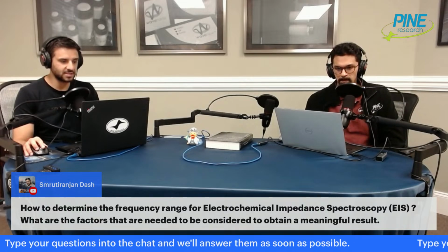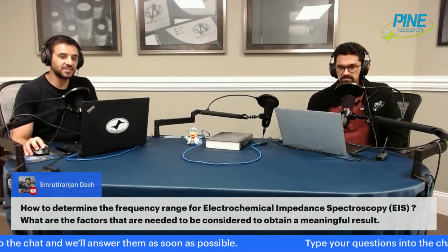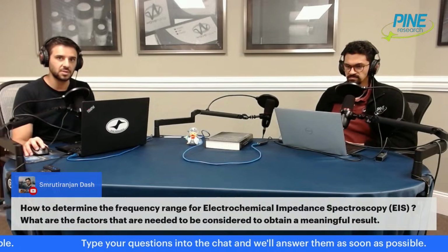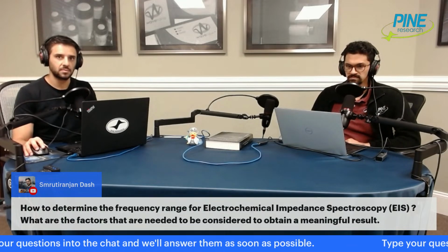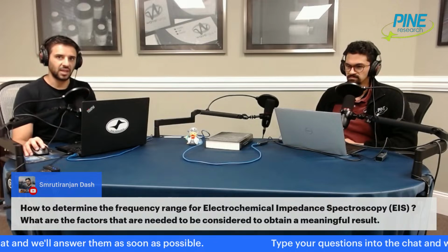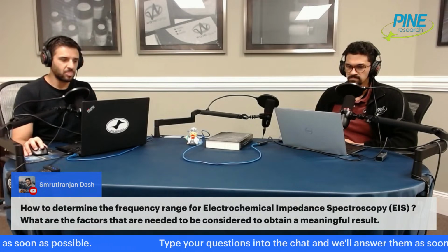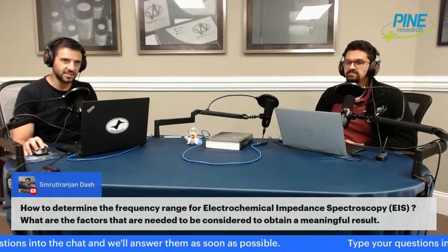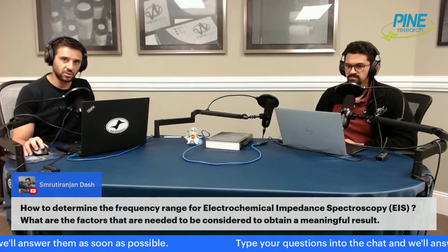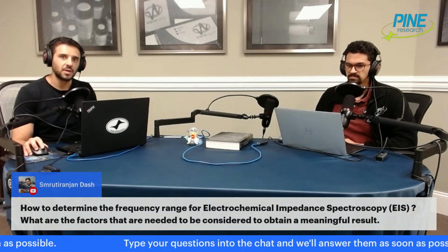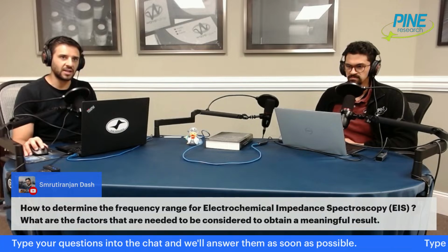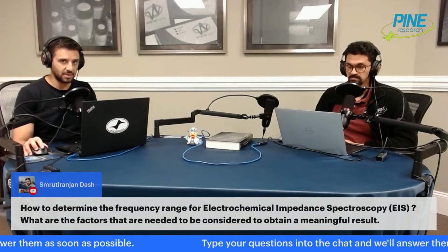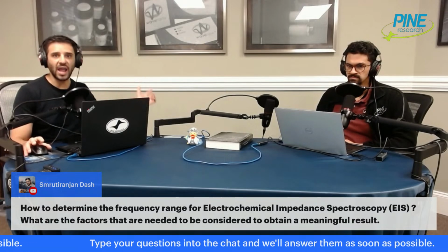What I would say as advice is exactly what Alex said: if you're wondering what frequency range you should use, 1 megahertz to 0.1 hertz, with 6 points per decade. If you're not sure, the beauty of impedance as an exploratory technique is that it's non-invasive. So if you're trying to figure out what frequency range is most appropriate, you will most probably not do any damage by doing too wide a frequency range.